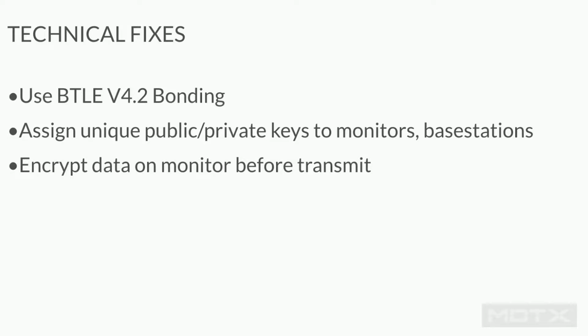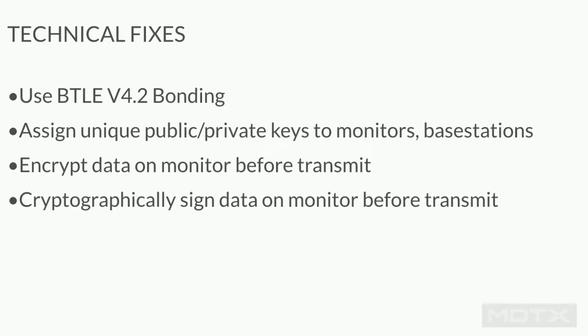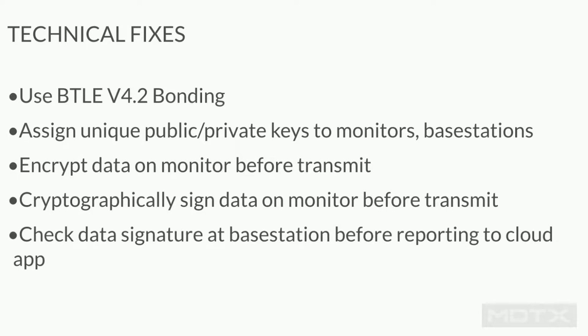You want to encrypt the data on the monitor before it is transmitted, ideally in the application layer. You want to sign that data cryptographically. Finally, you want to check the data when it's received at the base station to make sure that the cryptographic signature looks good, that nobody has manipulated this data, and that it came from a trusted source.